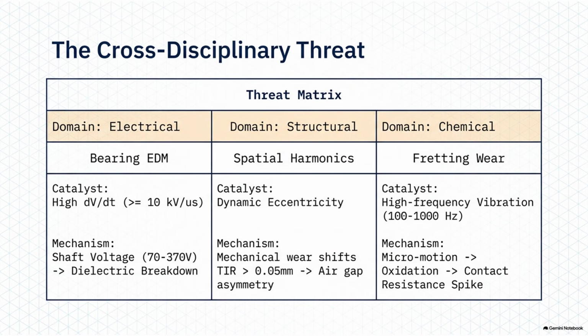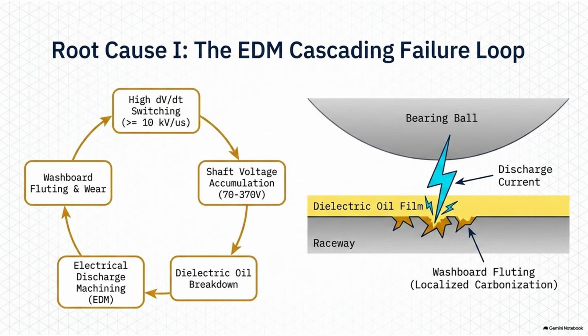Inside those bearings, you have an inner steel ring, an outer steel ring, and little steel balls rolling between them. But steel touching steel at those speeds would just grind itself to dust. Exactly. So the whole thing is packed with lubricating oil or grease. And oil is an insulator. Right. It has a specific dielectric strength, which is really just a fancy way of saying it can resist a certain amount of electrical pressure before it gives way. So as long as the shaft voltage stays relatively low, the oil film acts like a perfect protective wall. The electricity just can't get through. But because of that violent inverter switching, the voltage on the shaft spikes. It pushes harder and harder against that microscopic layer of oil, until the oil's dielectric strength just snaps.